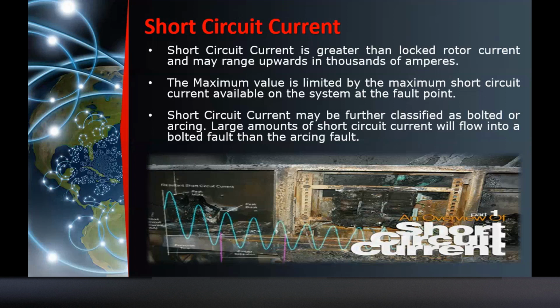Anong gagawin mo? Para makuha mo yung short circuit current, meron kang idea. Meron kang rule of thumb, meron kang initial information. Anong gagawin mo? Pwede mong gawin, pumunta ka dun sa transformer. Pumunta ka dun sa nameplate rating. Okay? Hanapin mo yung percent impedance. Then, from there, kunin mo yung rating, kunin mo yung full load current at the secondary, kasi dun magkakabit ng motor eh. And that full load current, divide mo doon sa percent impedance, the short circuit impedance. That is your symmetrical three-phase fault current at no load condition. So meron kang idea na pwede mong ibangga doon sa interrupting capacity ng secondary circuit breaker mo para magkaroon ka ng idea din na kung yung 100 horsepower is capable, na pwede pang idagdag doon sa system. Okay, so yan.